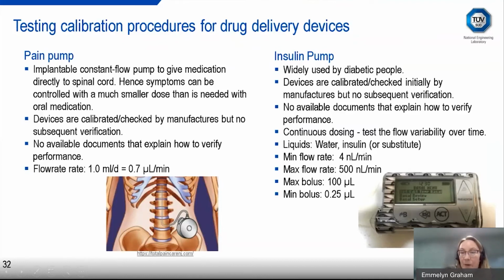With the insulin pump, we'll be testing that with water, but we're also wanting to test it with an insulin substitute, because it's always best to be able to test devices with the fluid that they're going to be used with. You can see that we're going down to very, very low flow rates, down to 4 nanoliters per minute for these devices.